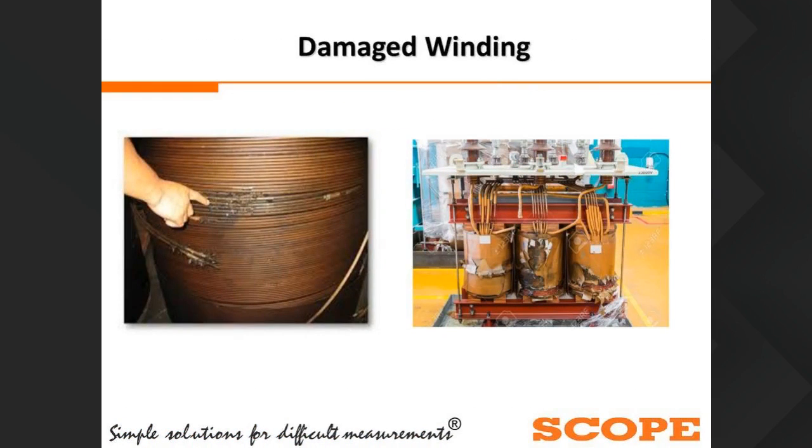So here you can see some peaks of the damaged winding due to the interturn short. You can see that due to the interturn short or hotspot, the short circuit happened.